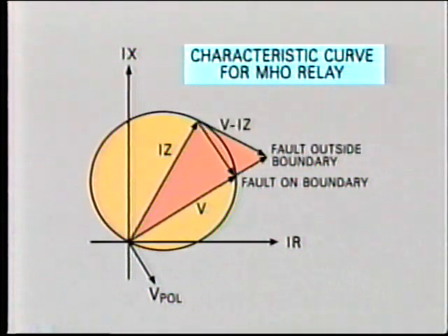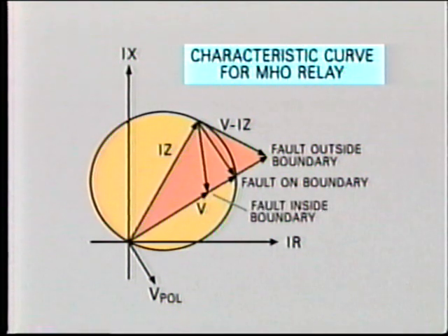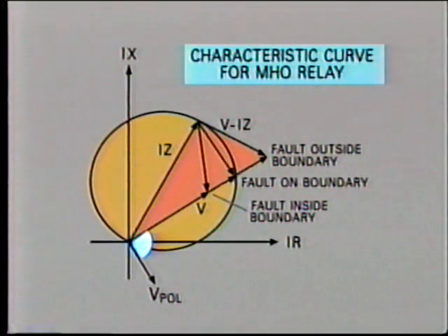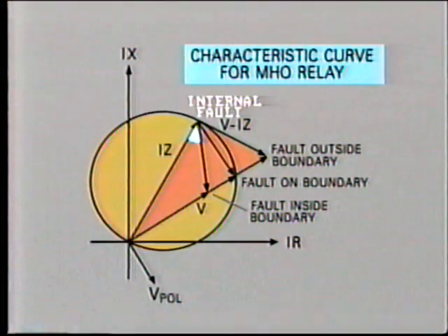For example, if the fault is external to the zone, V minus IZ will lie outside the circle. In contrast, an internal fault will lie inside the circle. Note that V minus IZ changes angle as the fault location changes. This changing angle is compared with a fixed polarizing voltage in order to determine whether to restrain or to operate the relay. The polarizing voltage is arranged to lag the line voltage by 90 degrees. You can see that an internal fault is indicated when V minus IZ lags the polarizing voltage. With an external fault, V minus IZ leads the polarizing voltage.